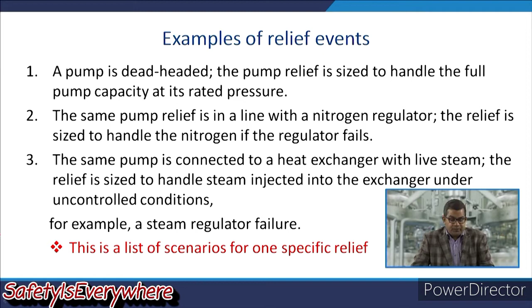Now if the same pump is connected to a heat exchanger with live steam, the relief is sized to handle steam injected into the exchanger under uncontrolled condition. So you can analyze all these three things where the pump is the same but the media is different. If the steam regulator fails, then this is a list of scenarios for one specific relief. Remember, the relief is the same, the pump is the same, but the media is different.